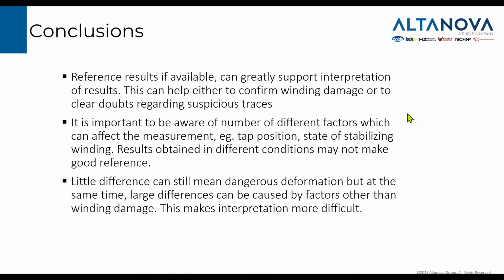So these are all the case studies which I presented, and I have some conclusions to this presentation. The first conclusion is that reference results, if they are available, can greatly support interpretation of results. So if you have the reference results, you should do everything you can to adapt your testing in such a way that reference results can be used. So the same tap position, the same condition of the transformer, and if something was described in previous reports, please apply the same settings and setup, maybe open or closed delta winding.